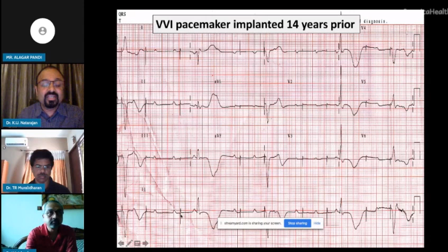That is because the battery has run out of its charge, and that is why there is erratic pacing. Some are capturing, some are not capturing. But the fact of the matter is there are spikes without depolarization. So this is an example of a capture failure and not a pacing failure. And this is another example. I'll stop with this particular example.